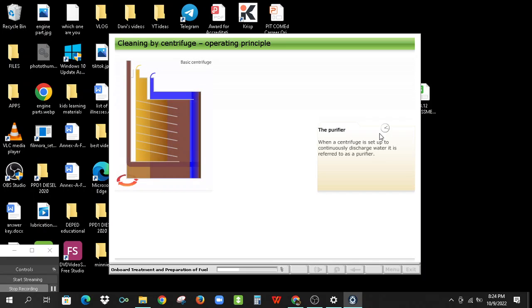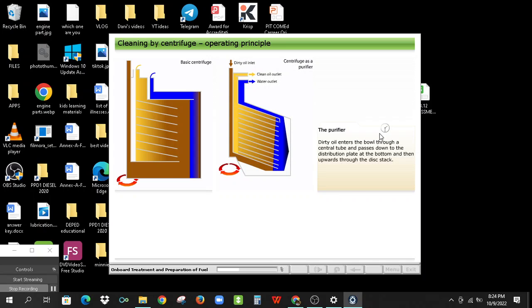When a centrifuge is set up to continuously discharge water, it is referred to as a purifier. Dirty oil enters the bowl through a central tube and passes down to the distribution plate at the bottom, and then upwards through the disc stack. The forces generated by the high speed of rotation cause the water and dirt, which are heavier than the oil, to move to the outer part of the disc stack and bowl. The water and dirt gather in a region between the wall of the bowl and just inside the edge of the disc stack. The clean oil gathers in the region from the center of the bowl to just inside the edge of the disc stack.